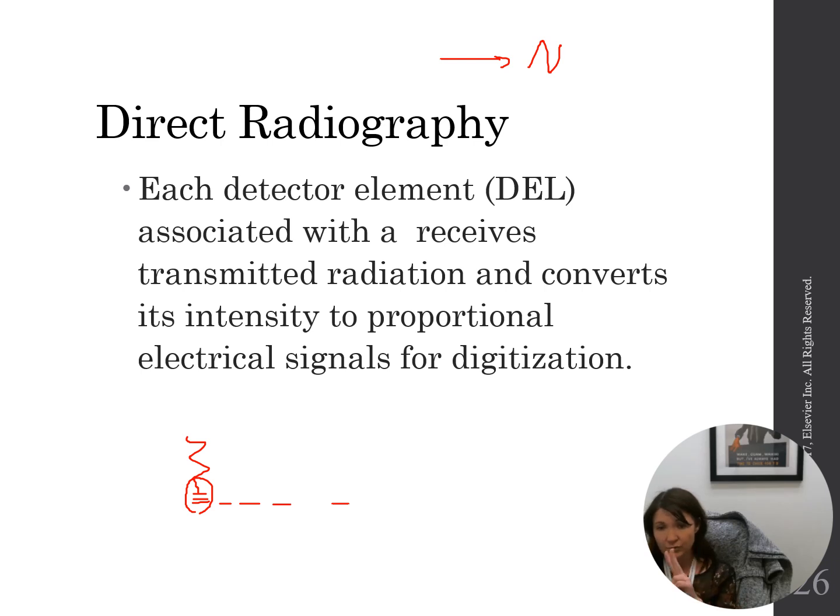So we have now free a positive and a negative ion. Those ions are going to be attracted to the different diodes, and the diode that is attached to the TFT is going to take the signal of those free ions, and that signal is then going to be stored in the capacitor and saved as a signal representative of the number of photons that interacted at that space.